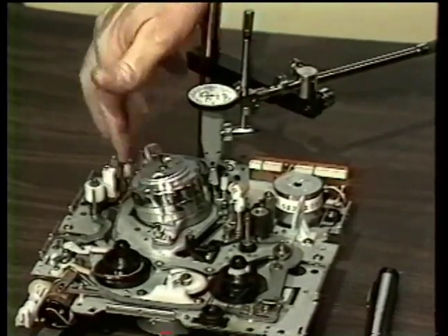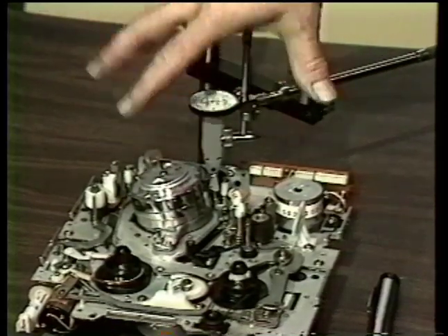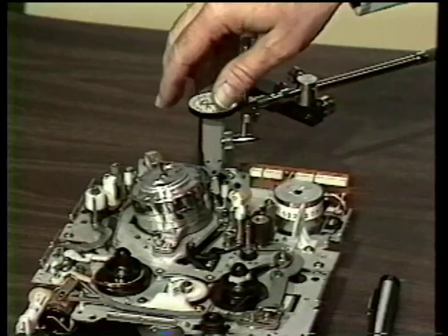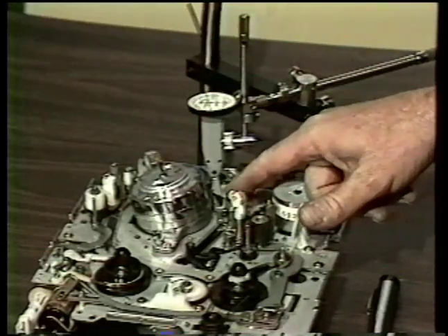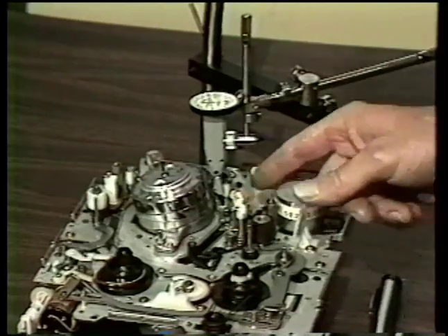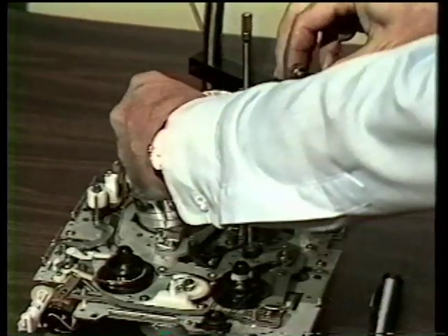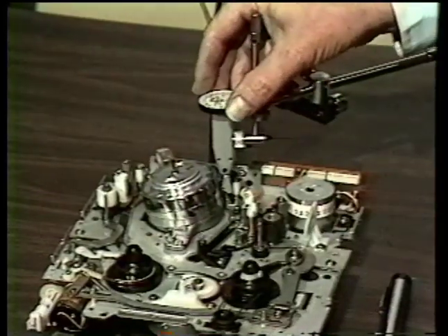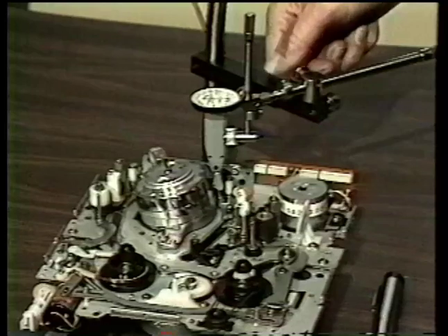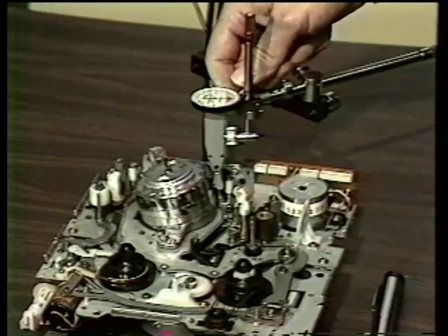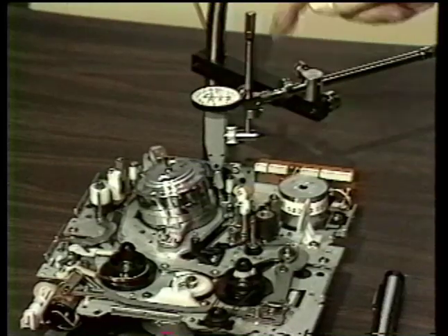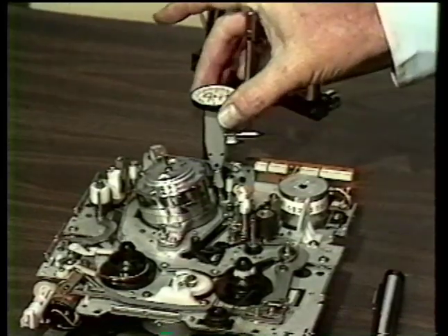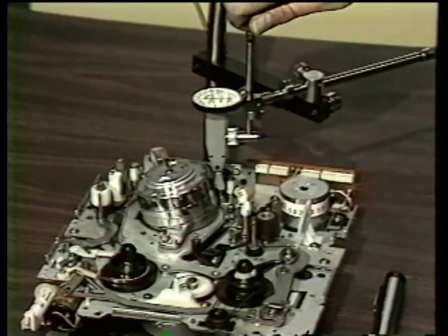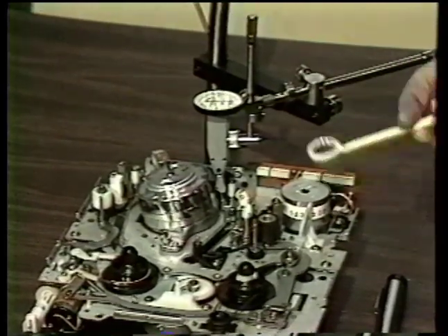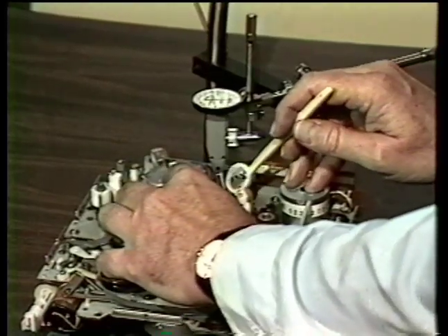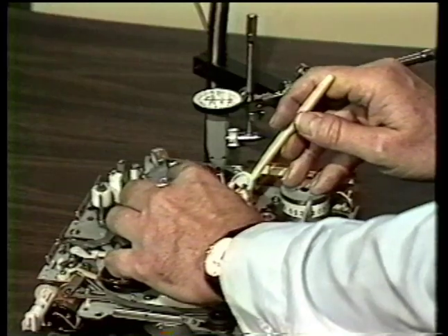Also, I've located the head tips out of the way while I'm doing the initial setup. This is to prevent any accidental crashing of our tip against the little drum. We want to make sure we're working very safely and not going to hurt anything. Once we get this positioned as close as it is now, make sure you just snug these two knobs down by hand. What this does is it makes this tight except for the adjustment knobs. So as we sight down the sighting groove, we actually will see the head tip at the end of the sighting groove.